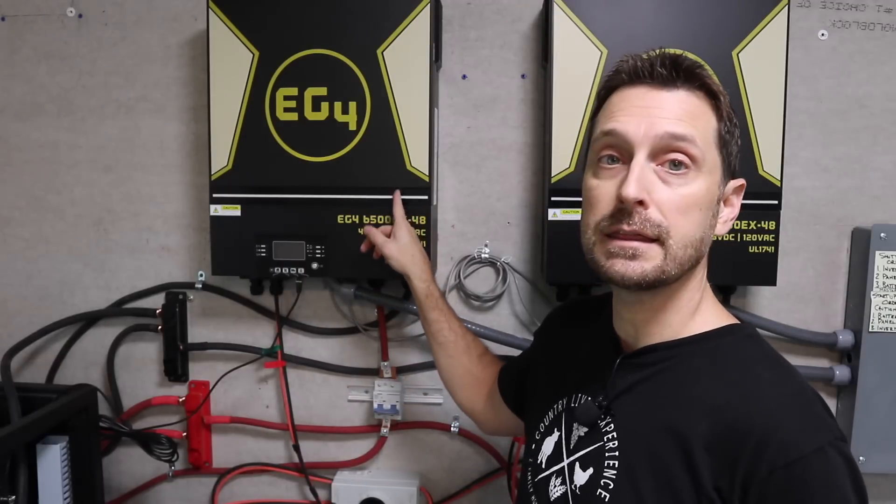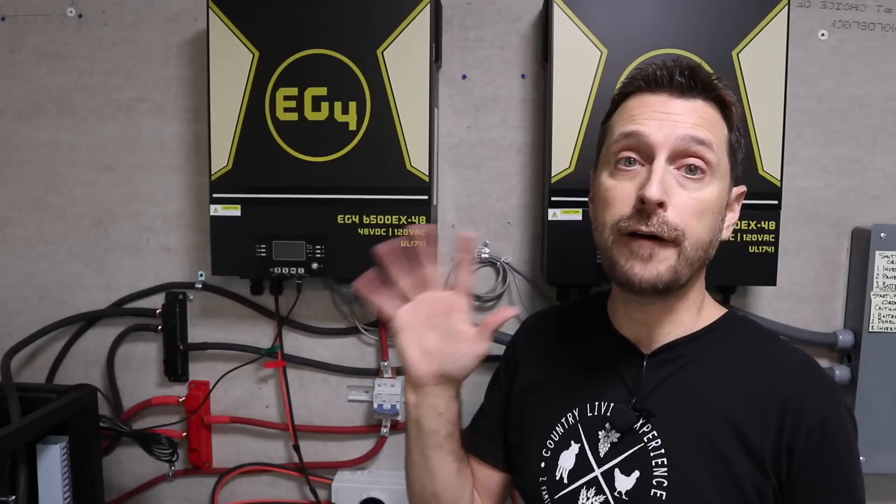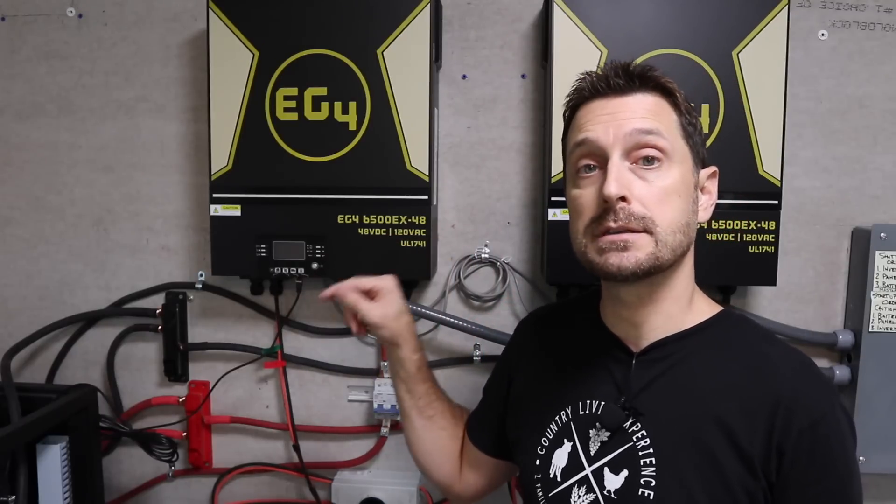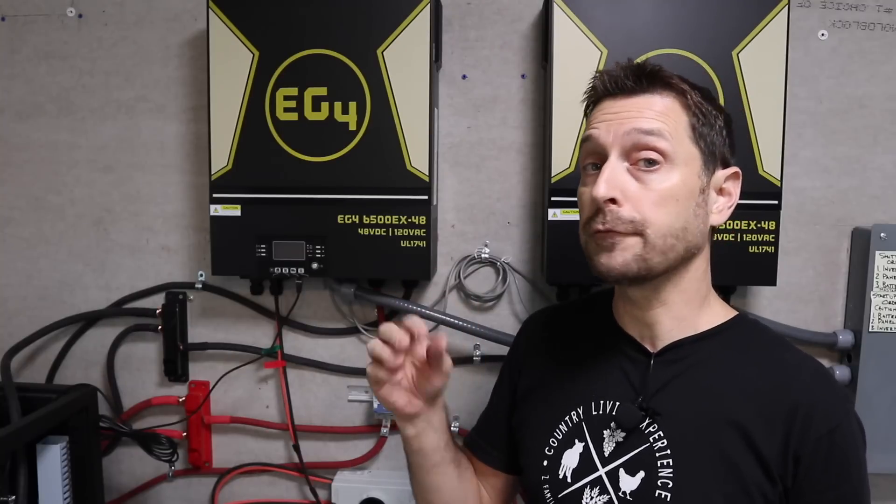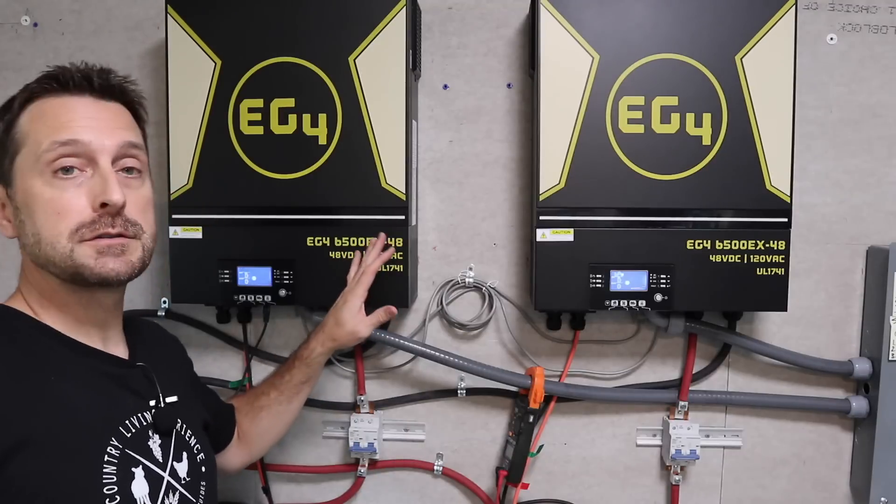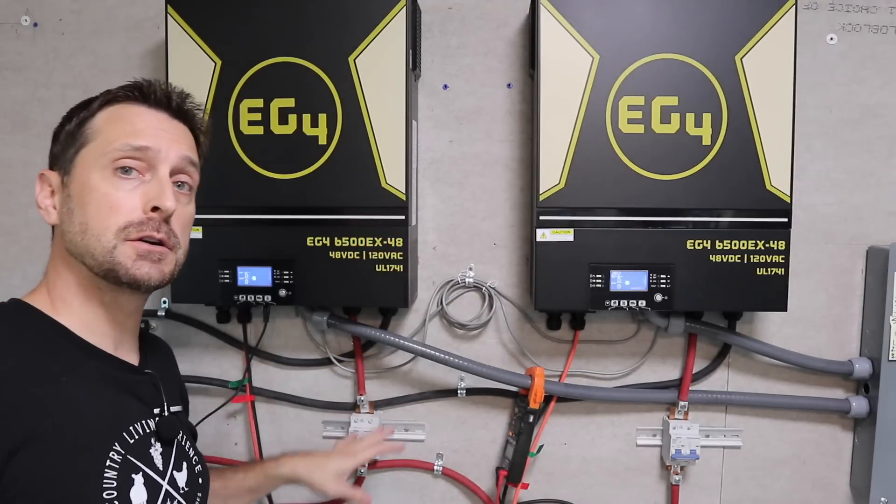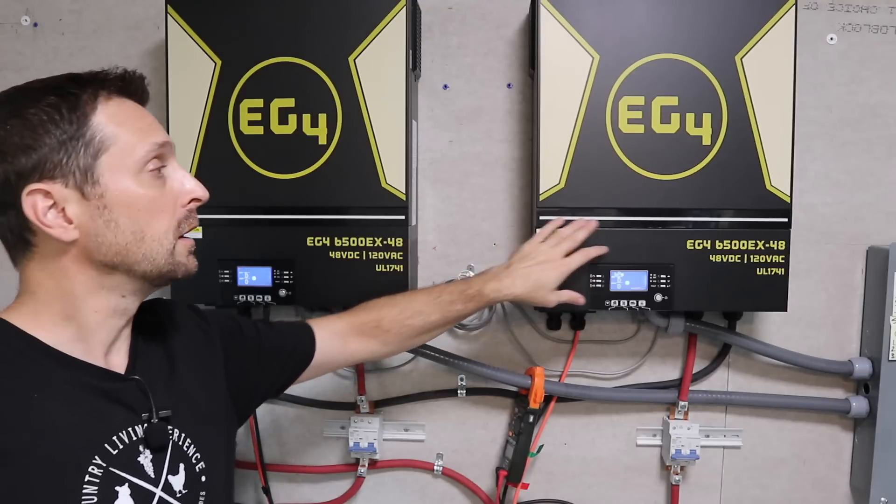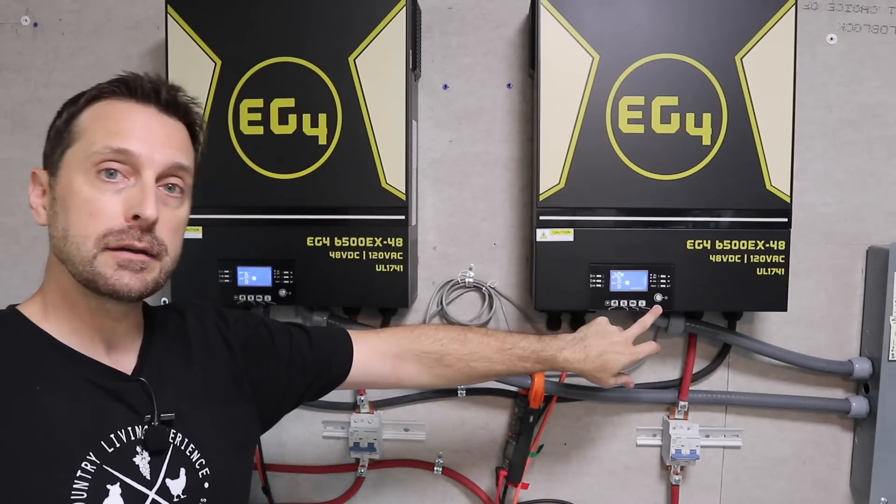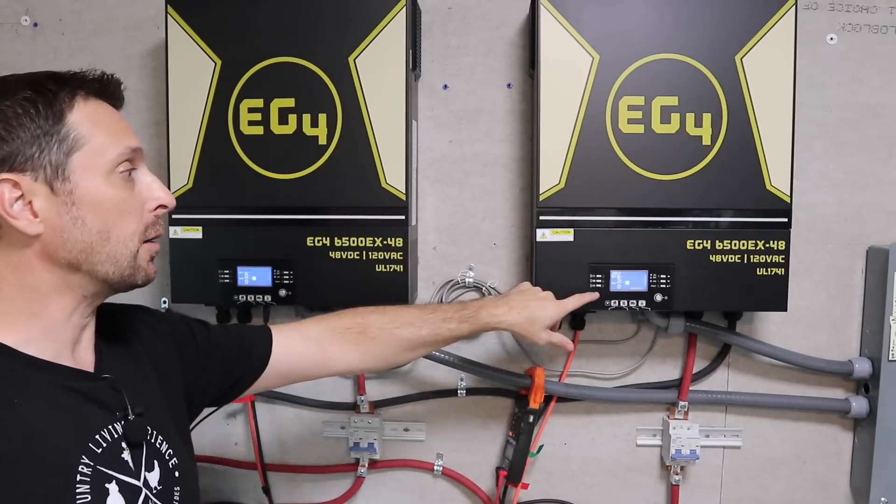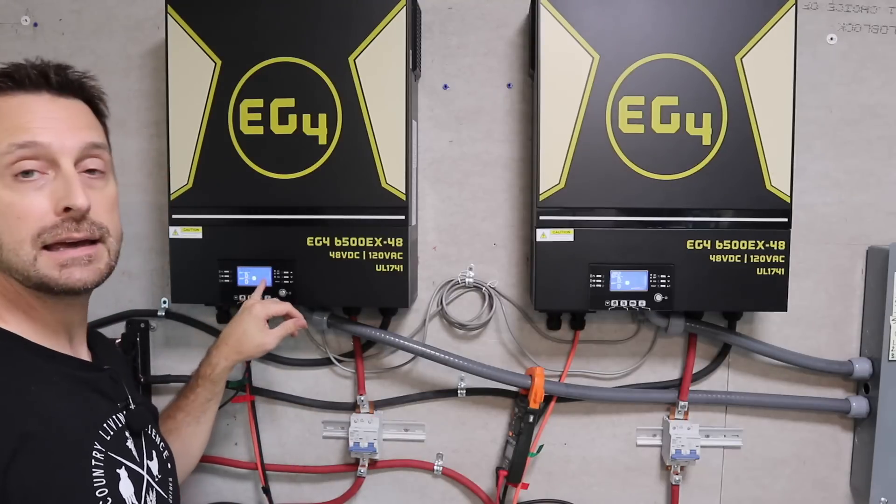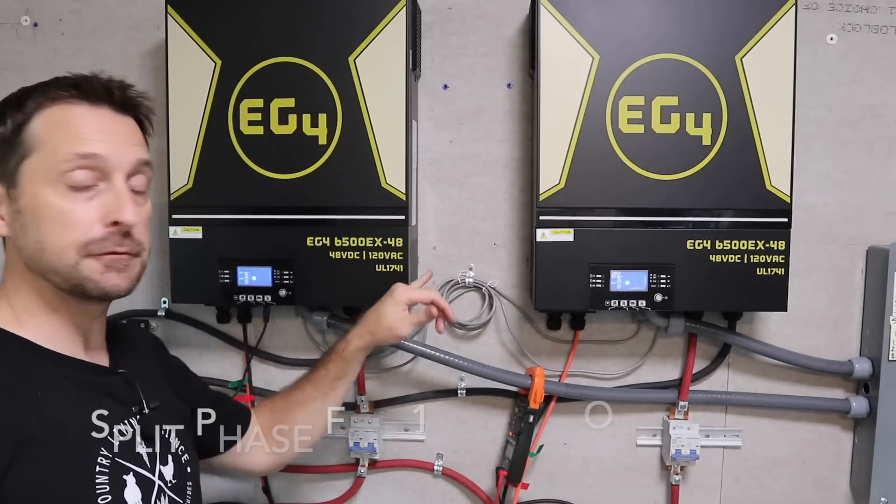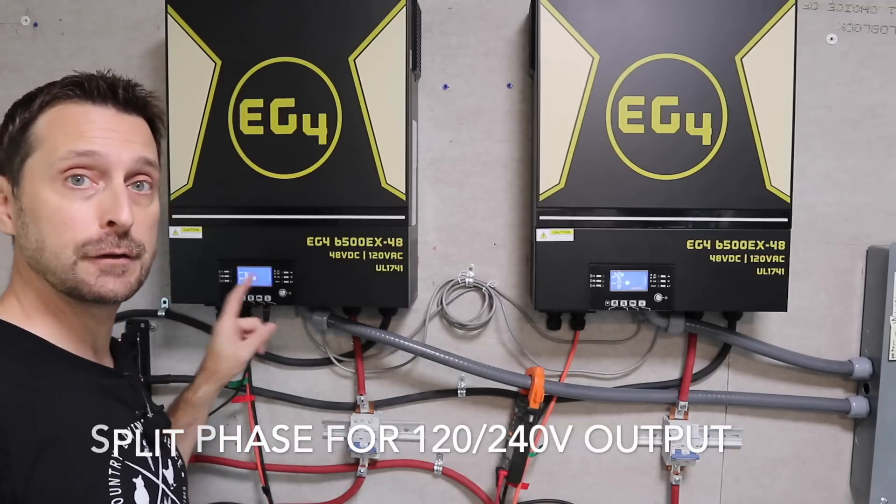For our initial setup, we're going to focus on three protocols. The first one is protocol 28, which is going to set these for split phase. The second is protocol five, which is going to tell it which batteries that we have. And the last one is protocol one, which we are going to set for our use solar battery utility in that order SBU. The best way to get the inverters to wake up in standby mode is to turn on your solar. We turned on the solar and you can see the inverters are not on. There's no colors going back here on this LED bar. We've got power to the screens and we need to get in here and change these so that they are split phase.